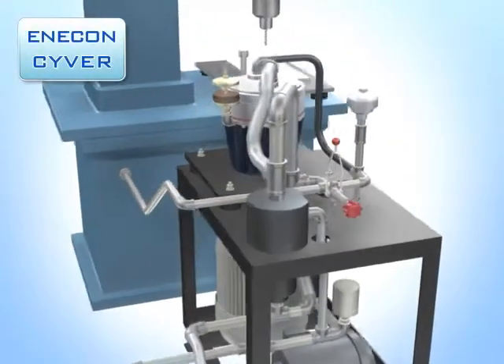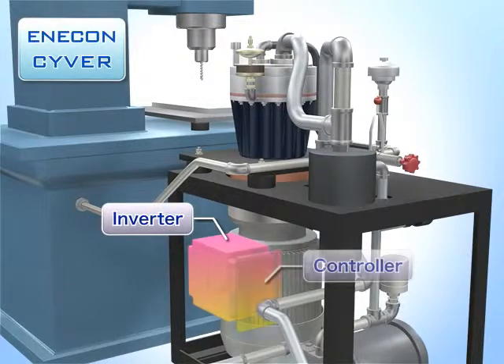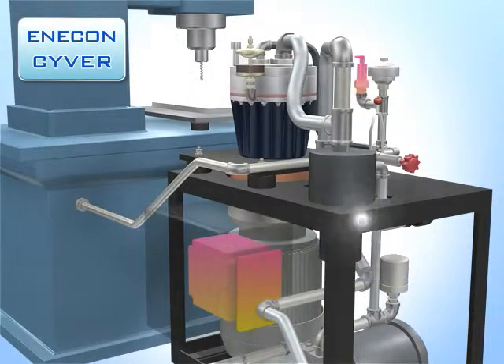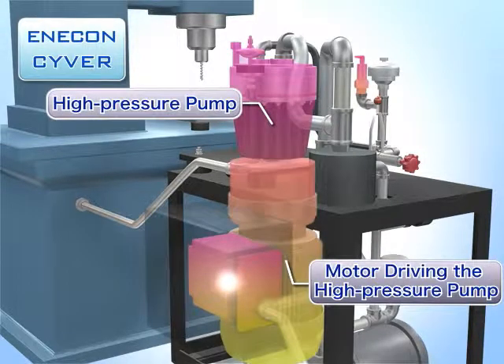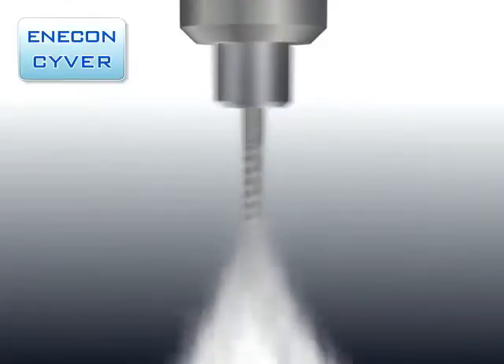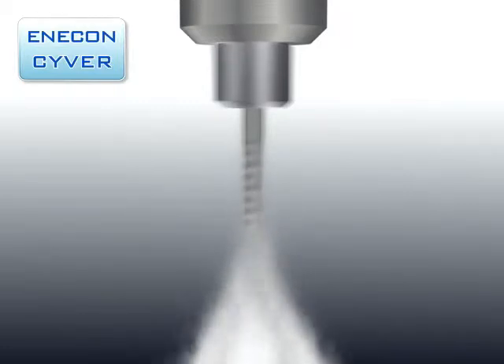By contrast, with the newly developed Enecon Cyver, Nikuni has achieved multi-stage constant pressure control by adding an inverter, a controller, and pressure sensors to the conventional high-pressure pump. The multi-stage control adjusts the pump's output power to ensure that the pump's discharge pressure is equal to the pressure required by the machine tool.